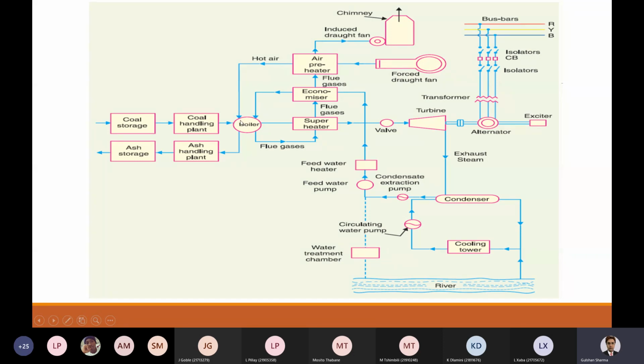So it means in the boiler you have the water, you have the hot water, you have the coal which is burnt, and now you need hot air also to burn the coal. That is why a forced draft fan is used, so that the air can be taken in. With the help of these flue gases only, you can see how efficient the process is: they use the flue gases which have come out of the superheater stage and the economizer, and then they take the air from the atmosphere, preheat this air, and only then feed it into the boiler.